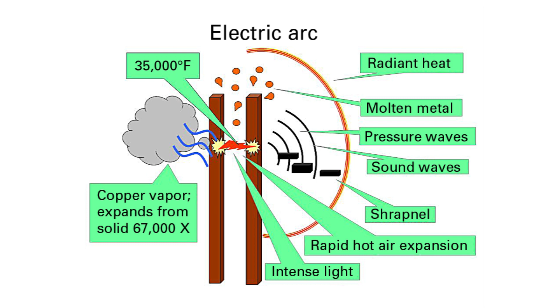In this test, an arc fault is initiated with a small piece of 10-gauge copper wire wrapped around three 1-inch copper anodes inside a 20-inch metal enclosure. The available 3-phase fault current is 22,000 amps at 480 volts. The fault current is cut off after 25 cycles, or approximately 4/10 of a second, or 400 milliseconds. As this clearly demonstrates, this is a tremendous amount of energy, and unless properly mitigated or protected, could seriously injure workers and damage equipment beyond repair.